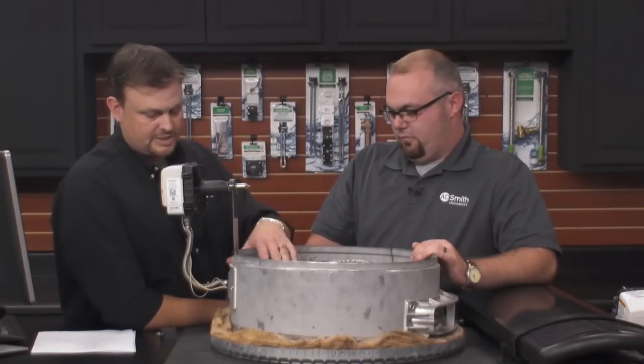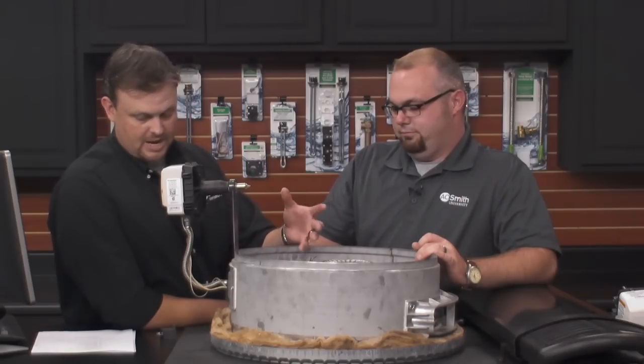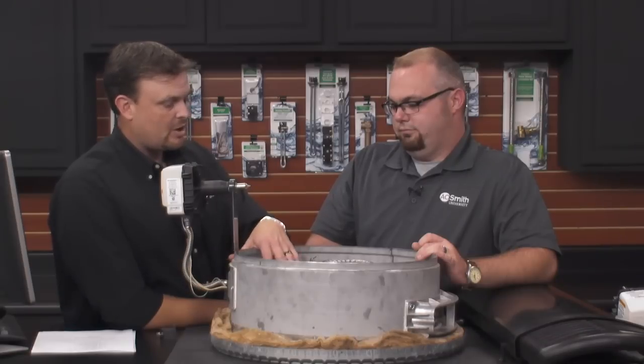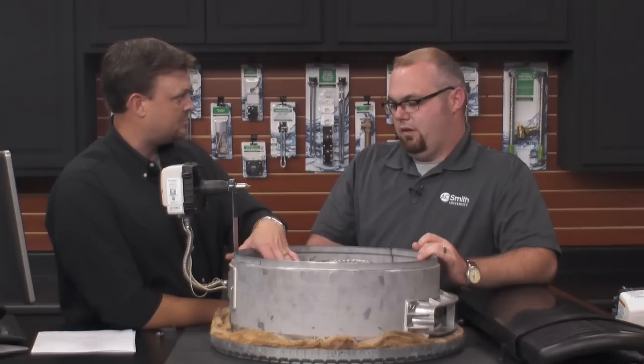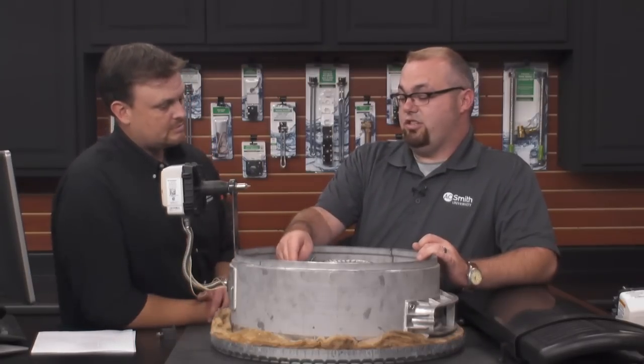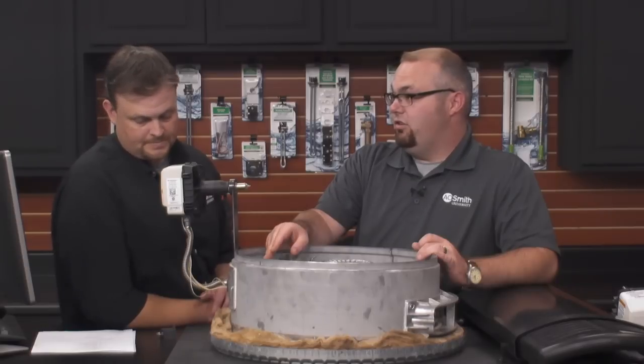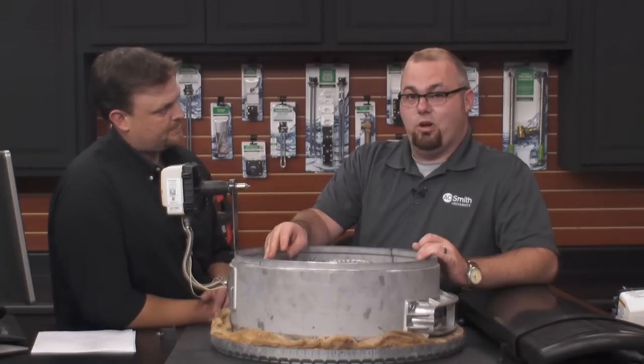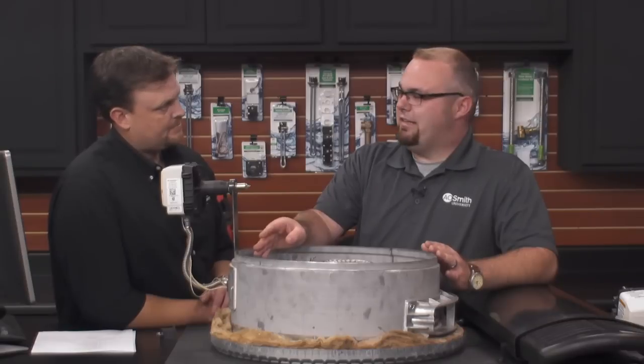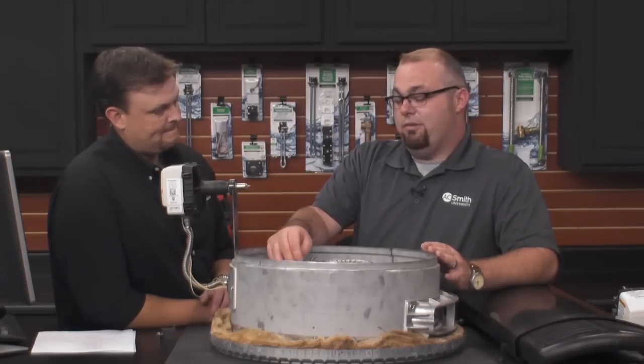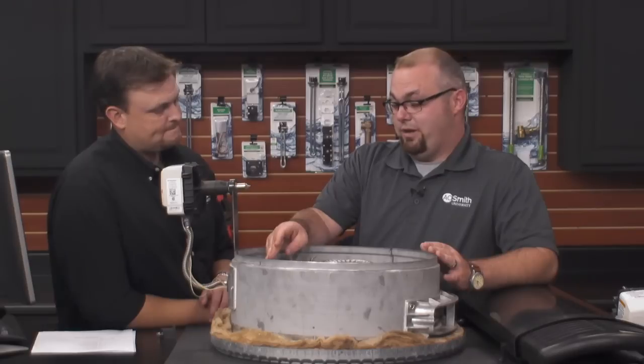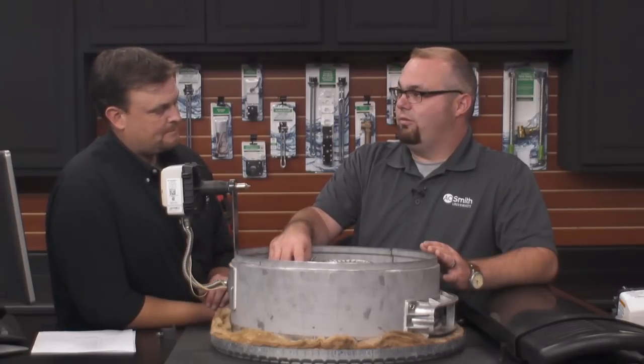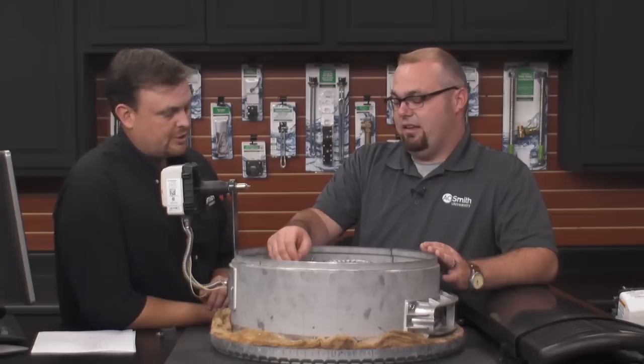And nothing's really changed about how they operate. They still warm up for 17 seconds and then we dump gas in there. When we ohm these out, when we're checking these, are these still 46 or so ohms? Well, this has actually changed. On the older units or the IntelliVent units, the hot surface igniter would ohm to usually 11.5 to 18.8 ohms at room temperature. This is a silicon nitride igniter, just like that, but this one ohms from 42 to 76. Okay, 42 to 76.